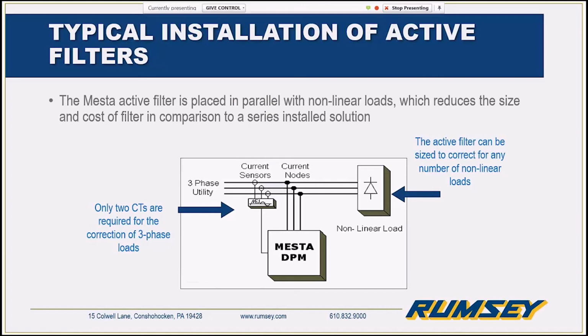And additionally, being installed in parallel, probably most importantly for many of our customers, is if there's ever a problem with the active filter, the process does not stop. There'll just be harmonic distortion for the day, the days, the years that the active filter just happens to be off.